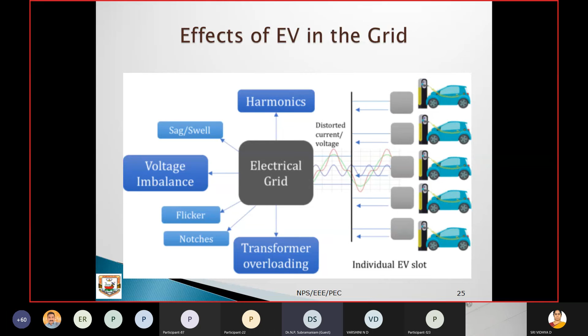Now, based on previous study, what are the common PQ disturbances? Reactive power demand, harmonic distortion, voltage sag and swell, voltage interruption, voltage unbalance, voltage flicker, notching, transient disturbance, frequency variation. Due to EV, mostly harmonic distortion is the major one, then sag and swell, voltage imbalance, flicker, and notching. These are also major issues due to EV.